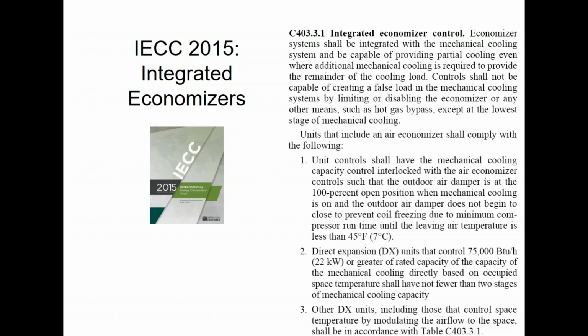So if you look at number 1 on the screen there in that section for integrated economizers, it'll tell you that the outside air damper has to go to 100% open whenever I've got mechanical cooling also engaged, right? If I'm in an economizer day.